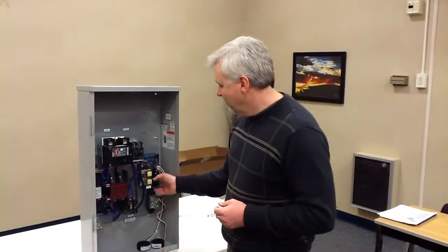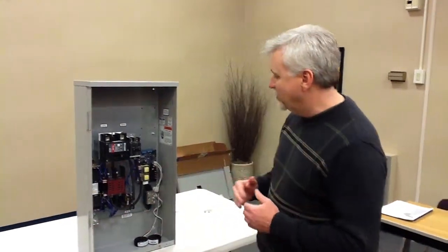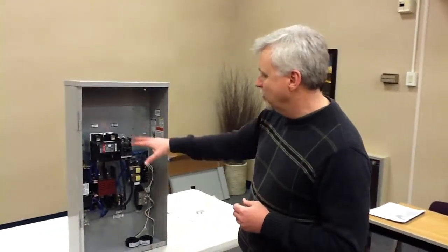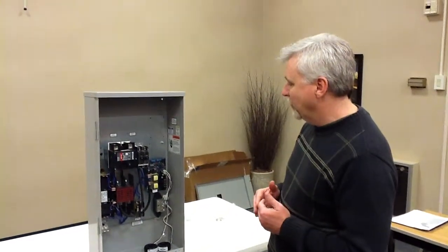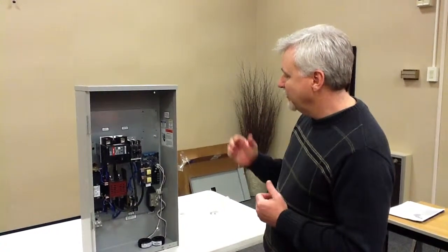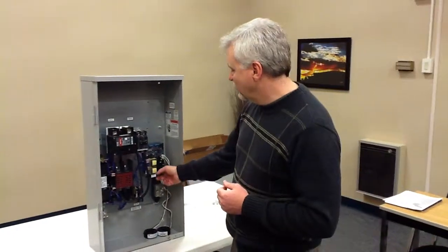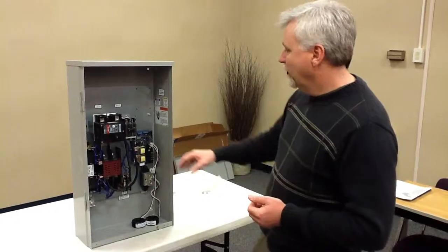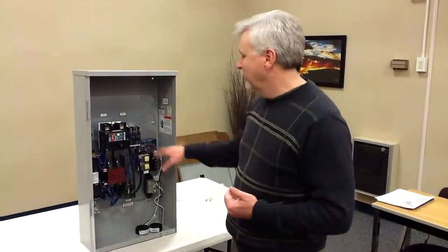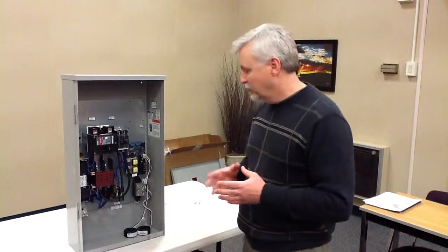The last time this came on, the current transformers were able to monitor the additional load that came onto the generator when that particular load kicked on. So now not only does it know what the generator's capacity is and what the current load is, it also knows what the additional load will be if this particular load is turned on. So therefore, this board can intelligently determine whether it can allow that air conditioner or whatever that load is to come on and not overload the generator.